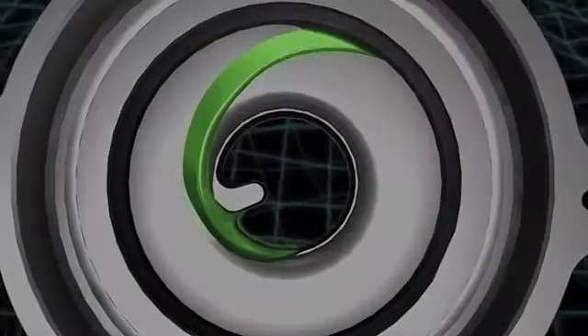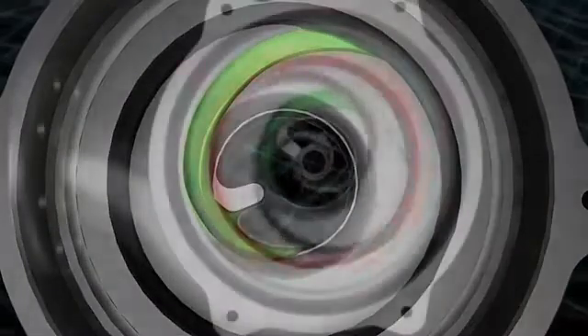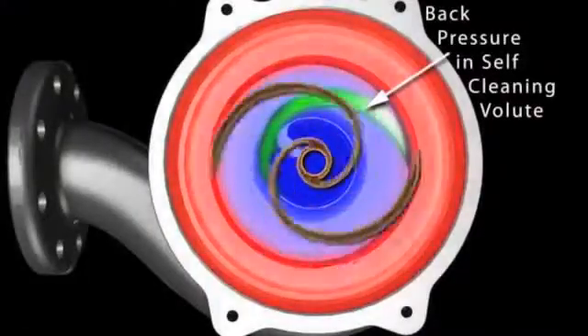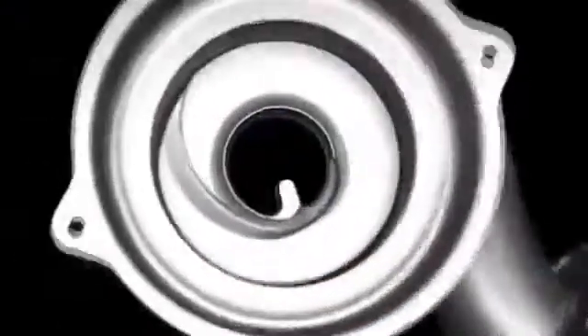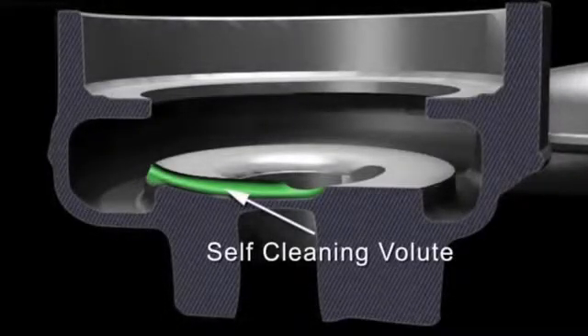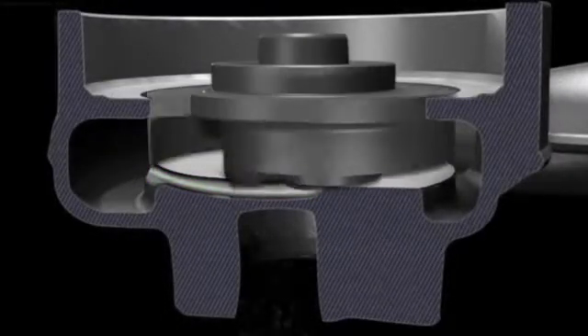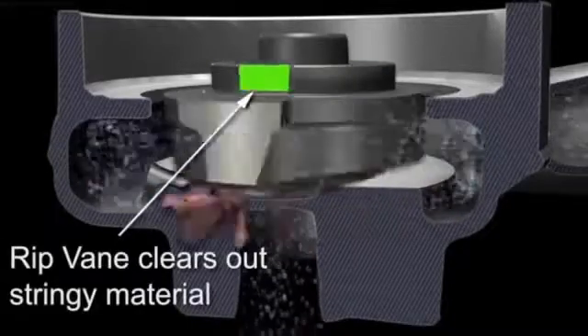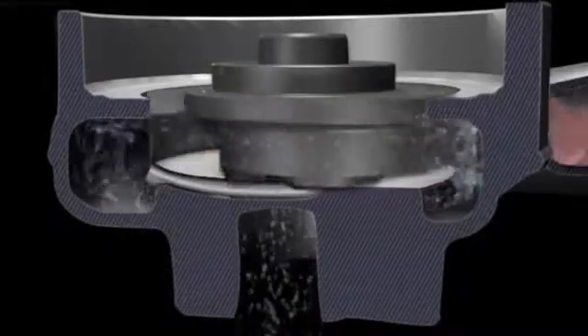The volute's improved geometric self-cleaning design helps solid material pass through the pump. This is accomplished by providing a passageway allowing debris to loosen from the impeller vane, slide outwards along the vane to the outer edge, and then be pulled through the pump volute. The resulting backflow cleans debris from the leading edge of the impeller and directs it towards the low-pressure center of the volute, where it re-enters the pump.